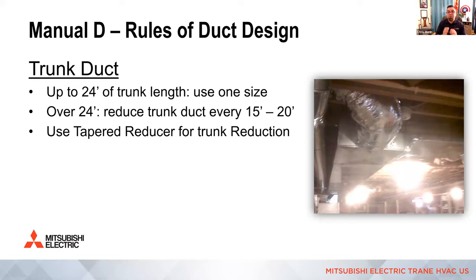All right. So rules of duct design. If you're having noise or airflow problems, you want to make sure all of these 10 or 12 things I'm going to run through are set first, before you start modifying volume of air or refrigerant charge or anything else with the system. If the duct design is incorrect or doesn't meet the rules of duct design, there's no adjustment to the system that you can make that's going to fix this. That's like having the wrong size system installed. You can't crank it way up or crank it way down and expect to get the right latent and sensible split and all the other design stuff. You've got to design the system right.